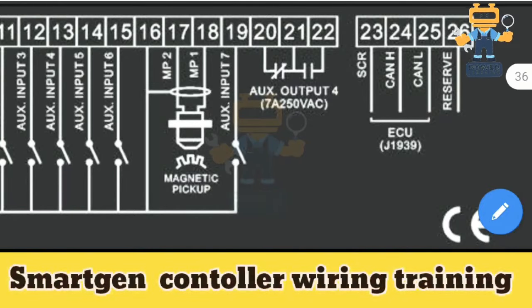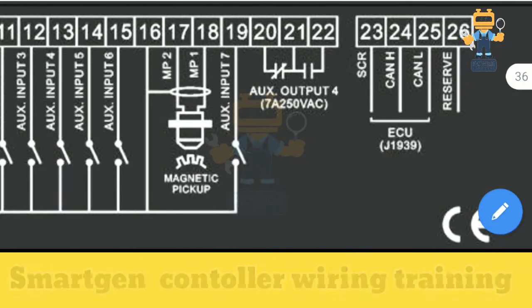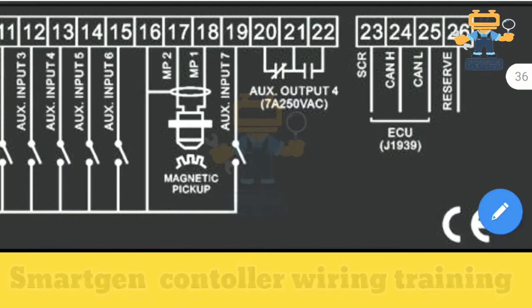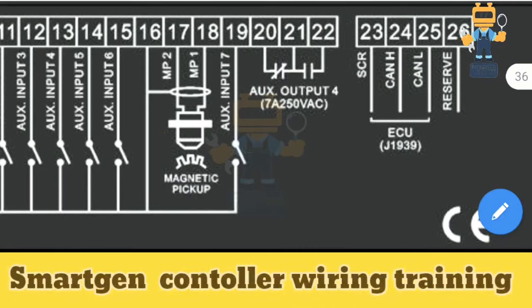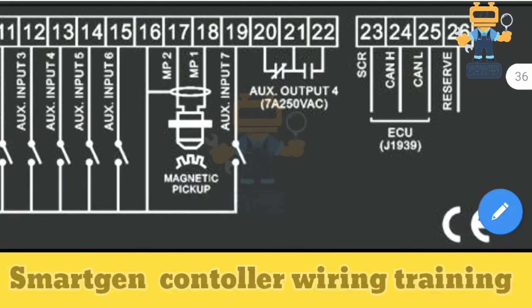Terminals 20, 21 and 22 are auxiliary output 4 — volt-free contacts rated 250V AC. From here you connect your AC voltage supply for breaker control. Terminal 22 is the common, terminal 21 is normally open, and terminal 20 is normally closed.